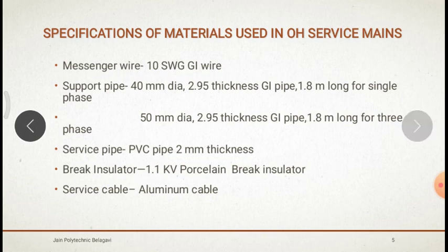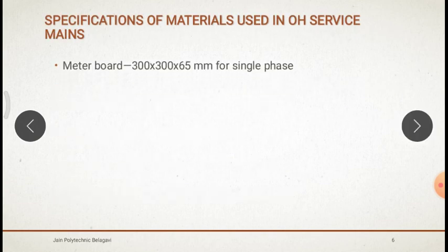Next we'll see about the meter board. The meter board is for the energy meter. Why are we using it? To measure how much electrical energy is consumed, for that we need the energy meter. But to fix that, we require a board, the meter board. If it is single phase, it is a 300 x 300 x 65 mm meter board. If it is three phase, it is 500 x 500 x 65 mm for the three phase.